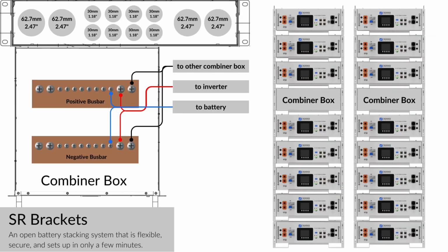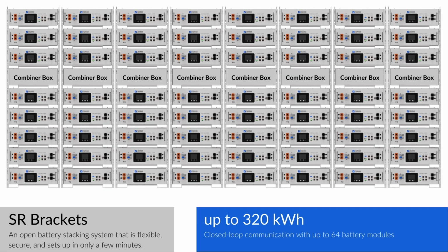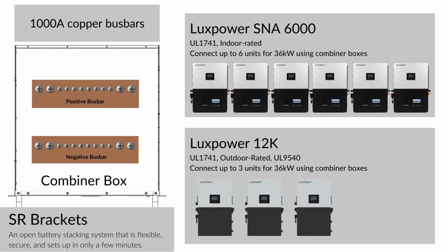In addition to these brackets, we offer a combiner box. Inside the combiner box, we have positive and negative bus bars rated up to 1,000 amps, and there's connection points that allow for cables to come in from the back of the combiner box, and then through this, you can connect multiple inverters. You can do multiple stacks. You can parallel combiner box to combiner box, and you can expand your battery bank to 320 kilowatt hours if you really wanted to, and still maintain closed loop communication. Because the copper bus bars are 1,000 amps, that allows you to connect up to 6 units of the SNA 6000, which would be 36 kW of combined power. If you wanted to use these units with the Luxpower 12K, that would be UL 9540 certified, and you would connect up to 3 units.